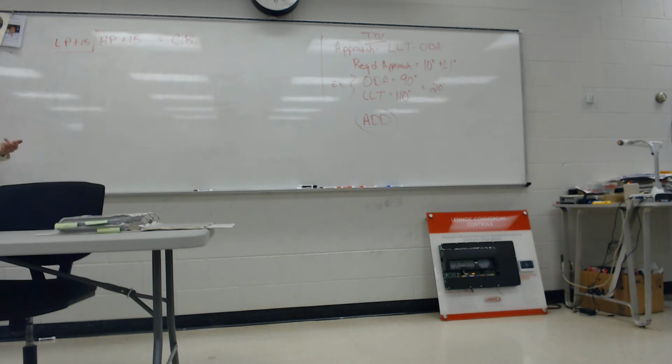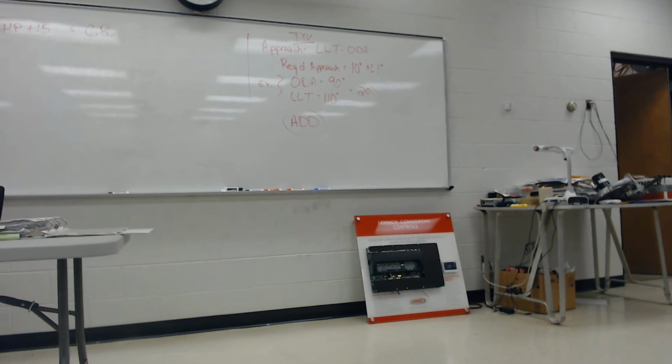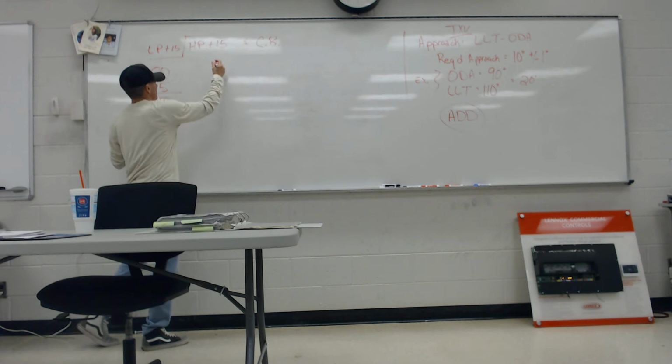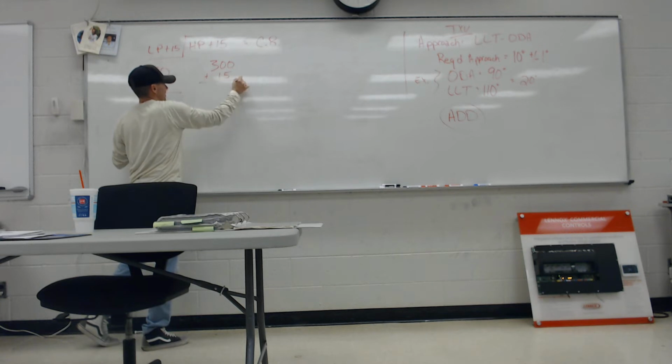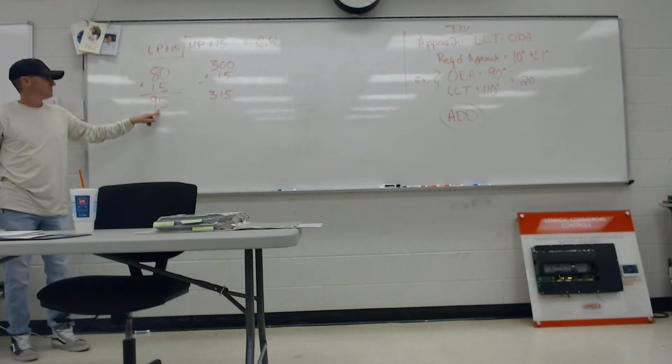In the residential world, and for air-to-air package units, it's like 3.5 to 1, like 3 or 4 to 1 compression ratio. So if my suction pressure, let's go R22 or something, let's say my suction pressure was 80. I add 15 to it for absolute pressure. So that's 95. My head pressure, let's say it was 300. I add 15 to it. I'm just throwing numbers out. That's 315. Now all I do is go 315 divided by 95.